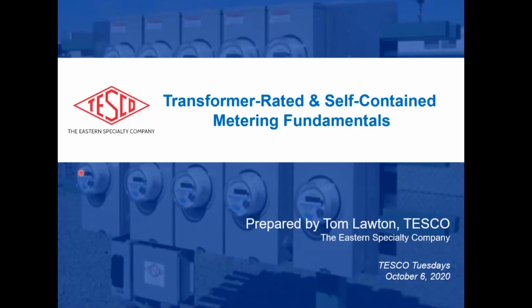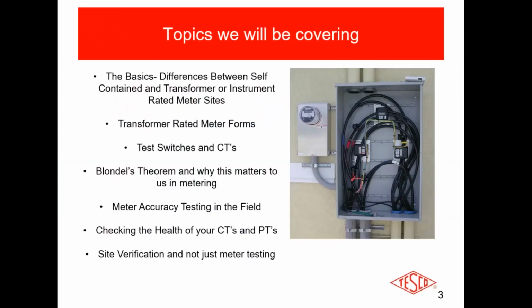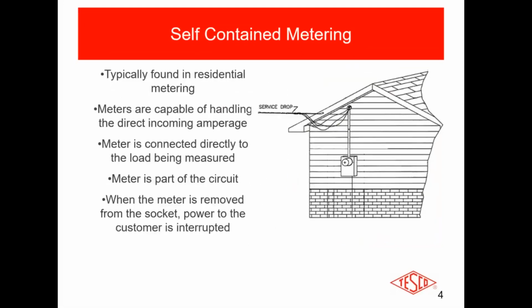All right. So topics we're going to be covering: the basic differences between self-contained and transformer-rated metering sites. Some of the different forms. We're not going to dwell a whole lot on that, other than to talk about the fact that there are a bunch. Test switches and CTs, Blondel's theorem and why it matters to us, so you're not going to get away from some of the math at least. Meter accuracy testing in the field, checking the health of your CTs and PTs, and site verification. It's not just meter testing or transformer testing. It's also about checking the entire site. Okay? So we'll start with the basics.